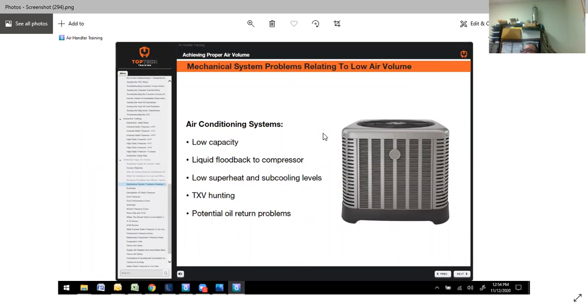Some mechanical problems related to low air volume are low capacity, liquid flood back to the compressor, and low superheat and subcooling levels. You can also have some TXV hunting issues, and a bigger one is potential oil return problems. That's going to cause wear and tear on your outdoor unit.